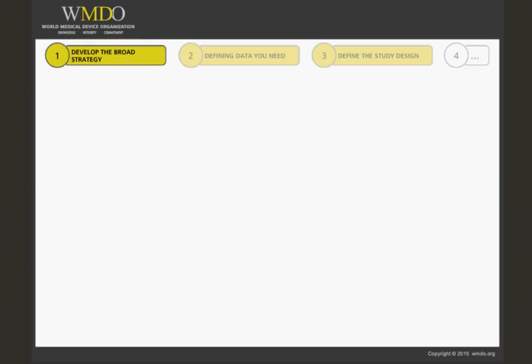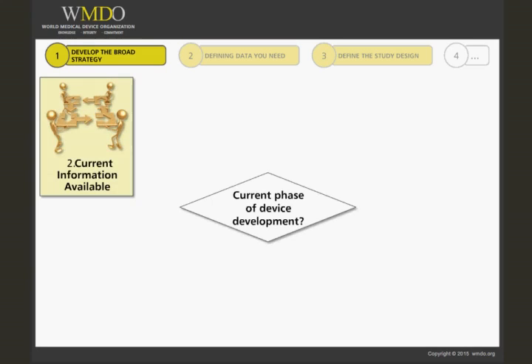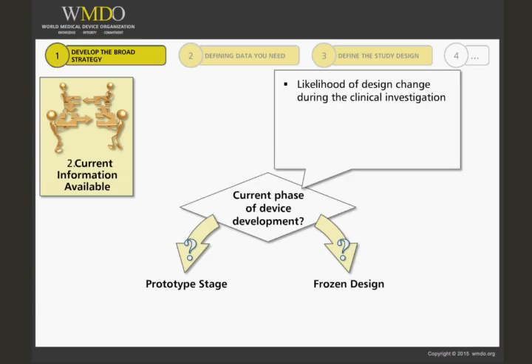Our second point is understanding the phase of device development we are in — in other words, how close are we to a final design, or a frozen design in our jargon. When planning a clinical investigation, we must take into account the likelihood of the need for a device design change. Work closely with research and development to get a feel for how prototype-like the investigational device still is, and evaluate whether possible design changes will be major or minor, and whether these will stop the clinical investigation or merely suspend it.